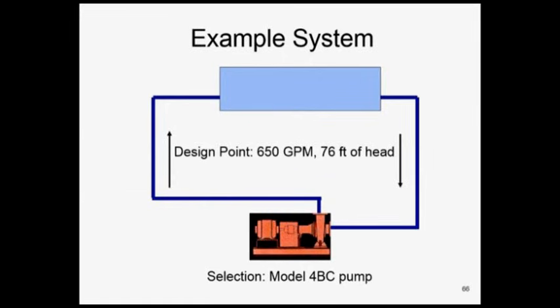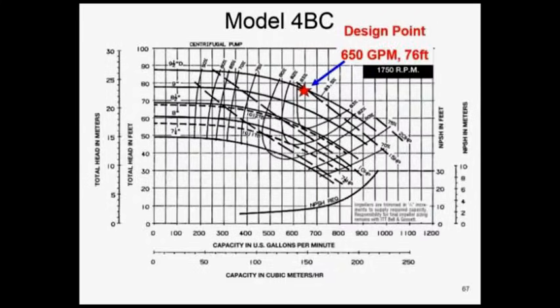Now, everybody understand this, and we're going to go back to a system curve. We're going to see how we're doing. We're going to start talking about balance a little bit here. So here we go. There's the pump. That little red star is the pump you purchased. That's the pump the engineer specified. That's the one everybody says we need. We need a flow rate of 650, reading straight down to the bottom.